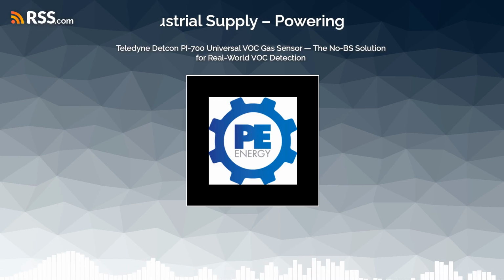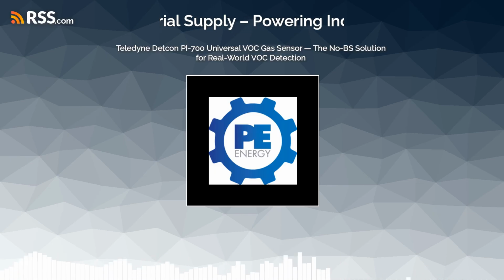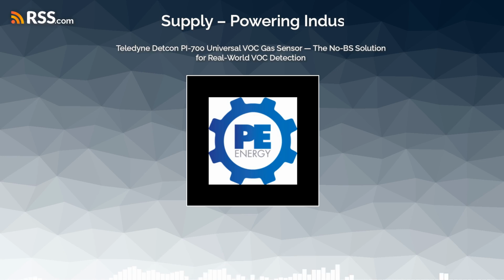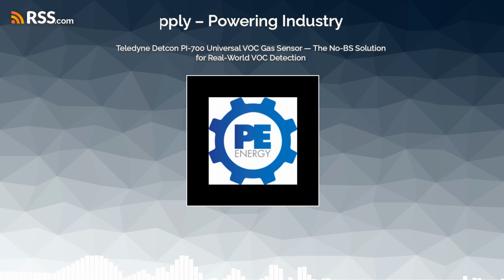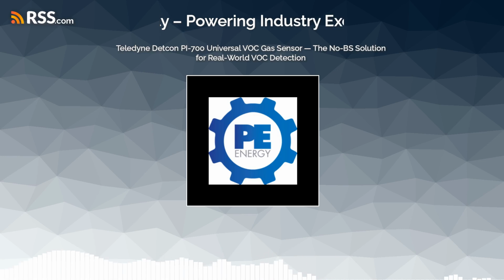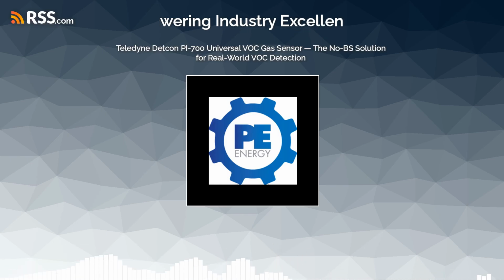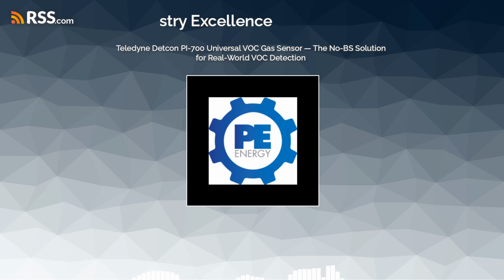Solid state means exactly what it sounds like, there's no liquid electrolyte to dry out. It's a metal oxide semiconductor. The gas interacts directly with the surface of the semiconductor and changes its electrical resistance, but it doesn't actually consume the sensor material in the process. So from an OpEx perspective, that's a game changer. You install it and you literally don't budget for a replacement until the mid-2030s. Assuming the plant's electronics hold up, yes, it changes the maintenance cycle completely.